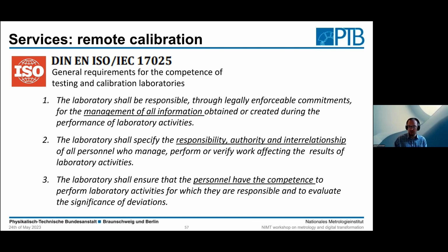So if you want to have a remote calibration service, you have to assess the competence of the software that is in place, if there is any software, or you as a lab are responsible for the competence of the people at your customer's place that help you with the parts of remote calibration that you can't do, like putting the right weight in place and so on. So you as a lab are responsible for the data that is used, for the responsibility and authority of the people in place and the software in use, and of the competence of the people in place and the software in use. So a remote calibration is possible, but I think it's very complicated. And I would say in most cases, it's much easier to not do a remote calibration, but do a calibration in a traditional sense, of course, made more efficient using digital technologies.